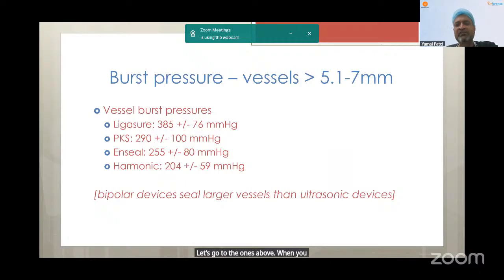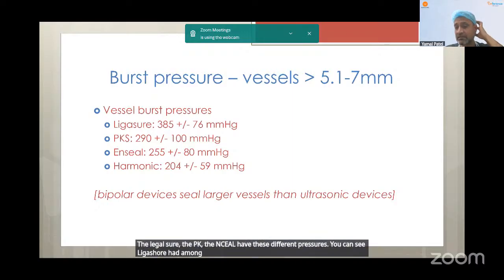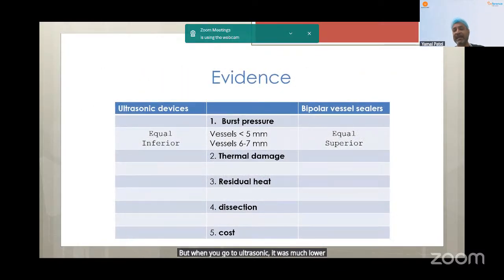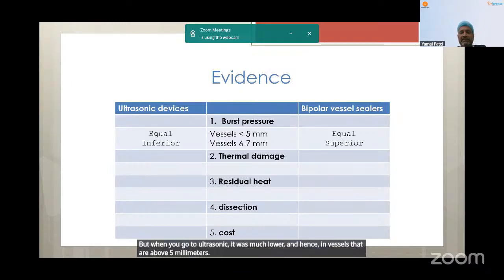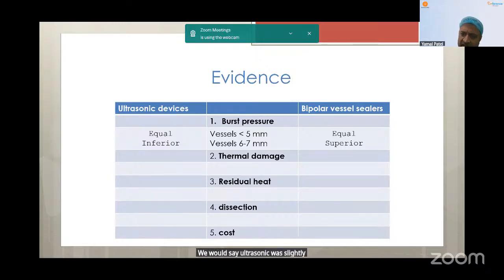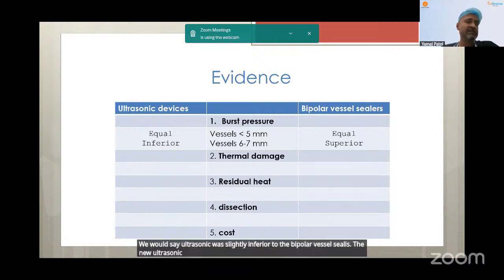When you go above 5 millimeters, the Ligasure, the PK, the Enseal have these different pressures. You can see Ligasure had among the best. But when you go to ultrasonic, it was much lower. And hence, in vessels that are above 5 millimeters, we would say ultrasonic was slightly inferior to the bipolar vessel sealers. The newer ultrasonic, like the Harmonic ACE and the 1100, definitely have a very good or equal burst pressure as well.